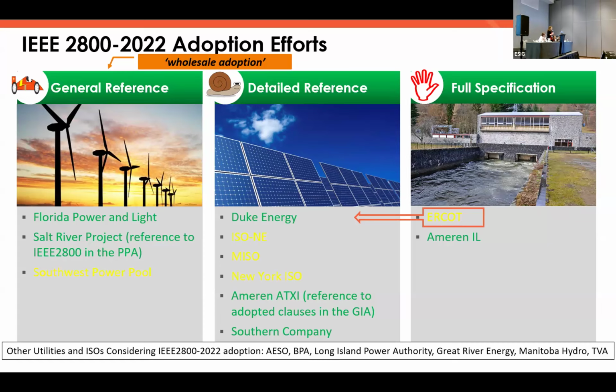So general reference adoption is basically thou shall be 2800. People just say, in the interconnection rules, 2800 now applies to all IBRs connecting at transmission level. And this is it, no more words there. Detailed reference is where there may be already existing interconnection requirements and they adopt certain clauses of 2800 and refer to these clauses in the respective documents. And then full specification is basically looking at your own interconnection requirements and borrowing some language from 2800 and adopting it into the document. So it's more work, more manual.